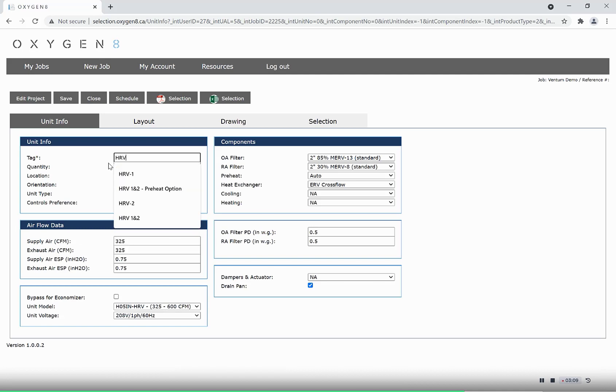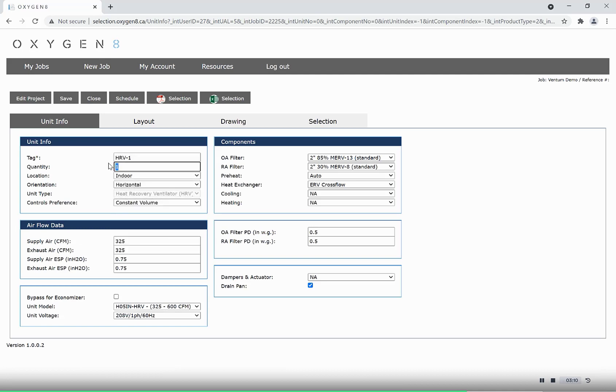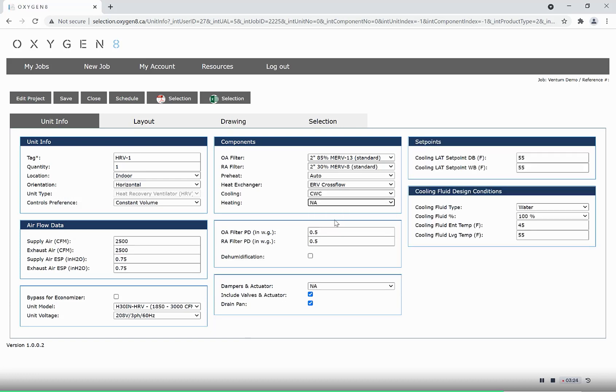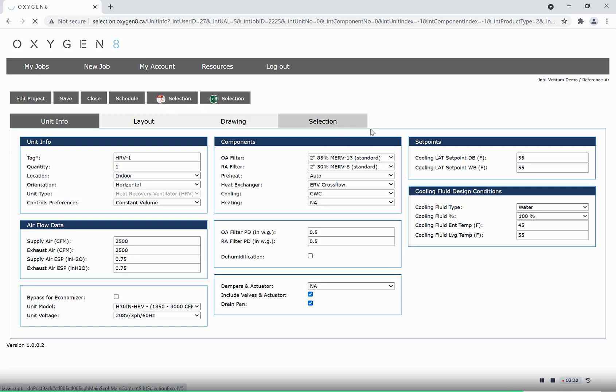For HRV, this process is the exact same. The main difference with an HRV is that there will always be a drain pan required. This is because it is sensible only recovery, and so there will be condensation that forms across the core.